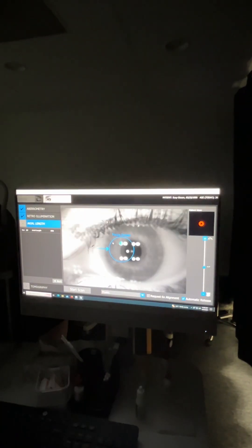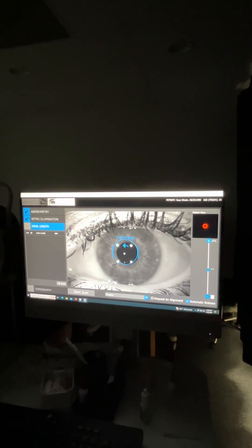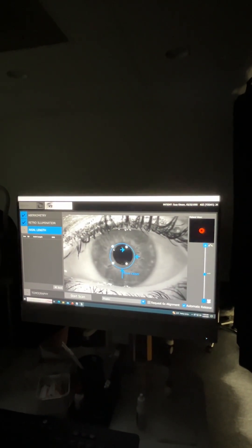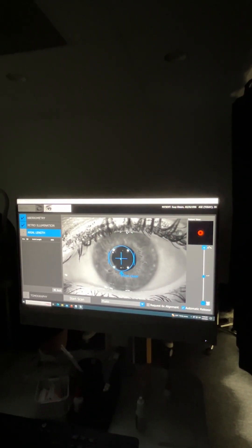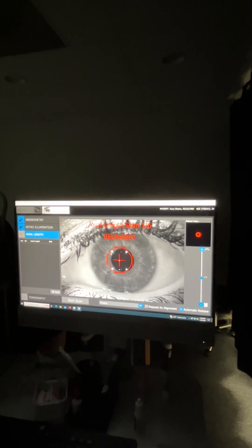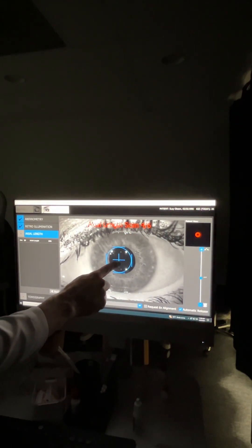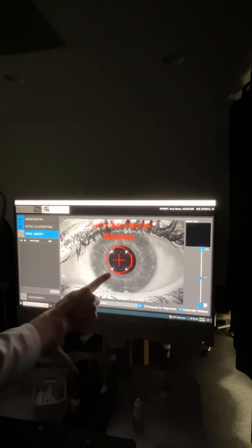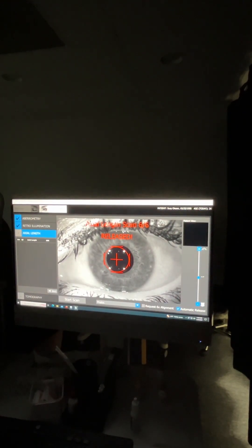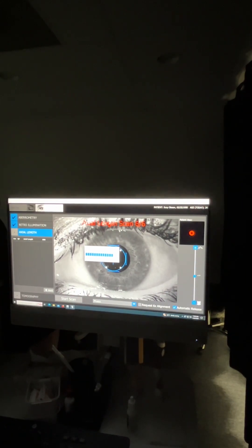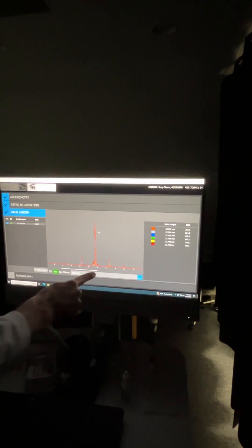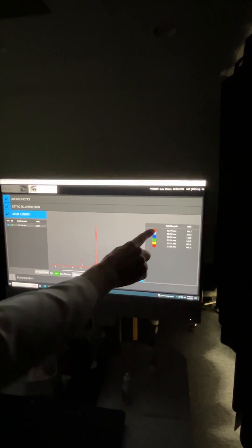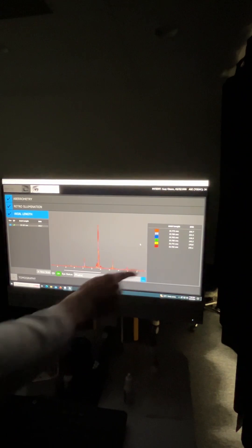Axial length. We'll select phakic. And then as soon as you look at the flashing red light, just be as still as you can. And then once the crosshairs meet that central dot, and then the bars are all around that circle, it'll automatically capture. We'll average that. Again, we have a nice signal strength. Again, Susie has very normal eyeball length. And then our grouping is very close together. Each of the colors represents one of the six scans.